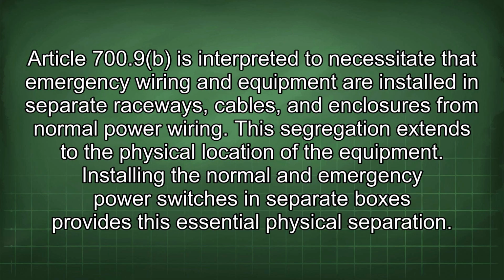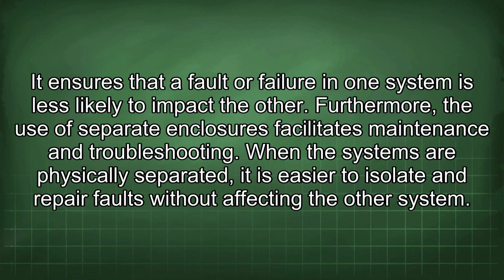Article 700.9 is interpreted to necessitate that emergency wiring and equipment are installed in separate raceways, cables, and enclosures from normal power wiring. This segregation extends to the physical location of the equipment. Installing the normal and emergency power switches in separate boxes provides this essential physical separation. It ensures that a fault or failure in one system is less likely to impact the other.